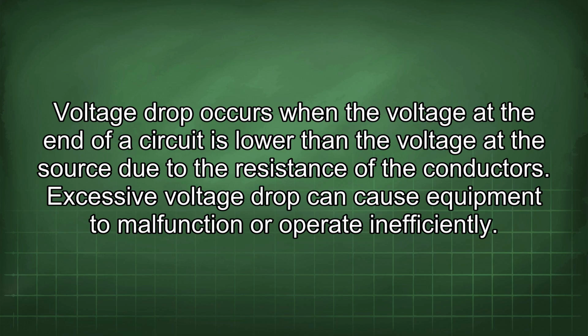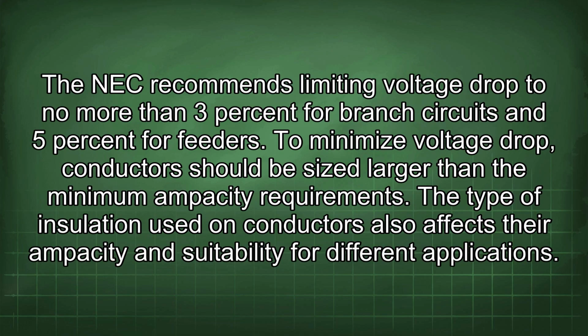Excessive voltage drop can cause equipment to malfunction or operate inefficiently. The NEC recommends limiting voltage drop to no more than 3% for branch circuits and 5% for feeders. To minimize voltage drop, conductors should be sized larger than the minimum ampacity requirements. The type of insulation used on conductors also affects their ampacity and suitability for different applications.